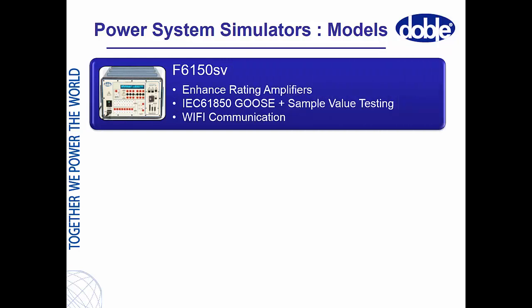Let's discuss the different models available for the F6000 family of power system simulators. The F6150 SV model is ideal for testing IEC 61850 protection, as well as protections that require high power and high current. It provides optional features such as enhanced rating current amplifiers, IEC 61850 sample value and GOOSE testing functionality, as well as Wi-Fi communication. Both copper and fiber optic ports for IEC 61850 sample value testing are inbuilt. The F6150 SV also has a wireless Ethernet port for additional test flexibility.